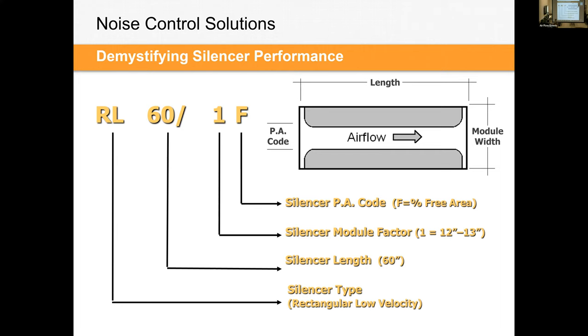Obviously the extended casing is just going to be on the side with the baffles, but in a situation where you have baffles on all four sides, can they do extended casings? You can, yeah. 6 inches? Yeah. So again, the top and bottom media is more of a special thing. You can't do that directly in the software. We do provide it a lot though, and we call that a rectangular cladded silencer where it has acoustic media on all four sides.